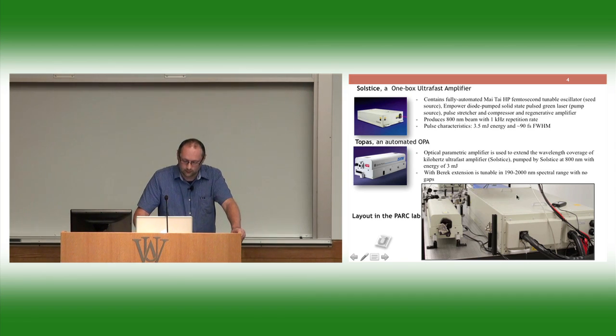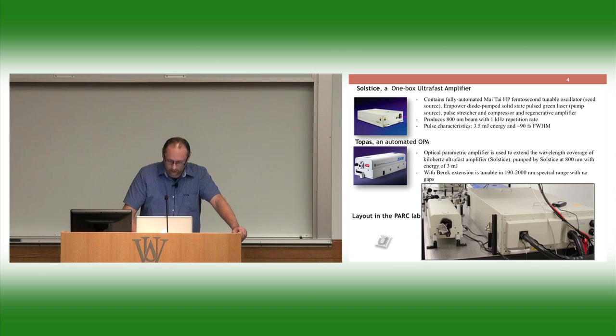The pulse width, which is really important because that defines the resolution of our instrumentation, is around 90 femtoseconds. The smaller box on the left side is TOPAS, an automatic OPA. We can get only one wavelength out of the box, so we need to use this wavelength to generate another wavelength that we want to use for excitation of our samples. OPA means optical parametric amplifier. Using just one wavelength on the input, you can get a quite broad range of excitation pulses out of the OPA: everything between 190 nanometers and 2 microns.